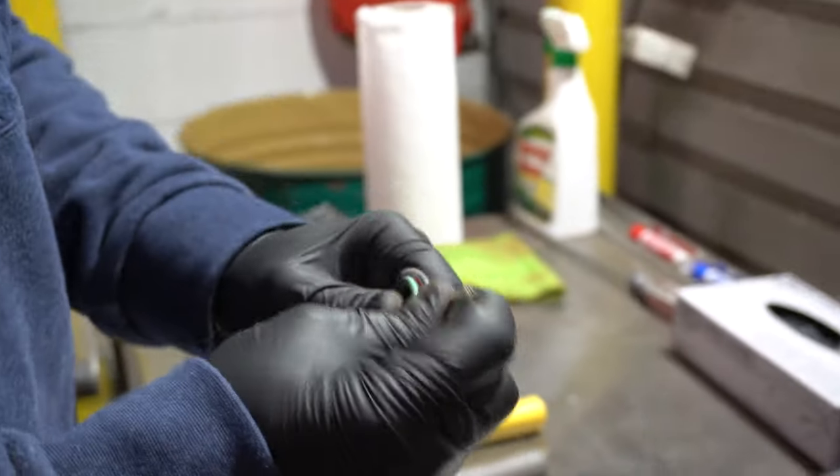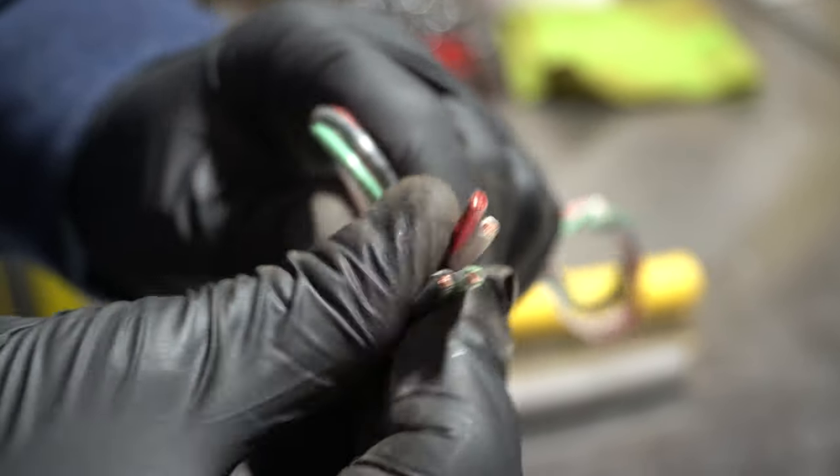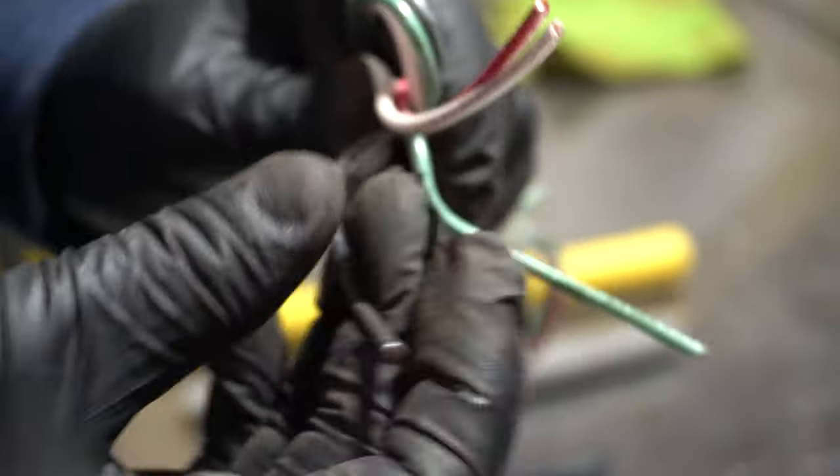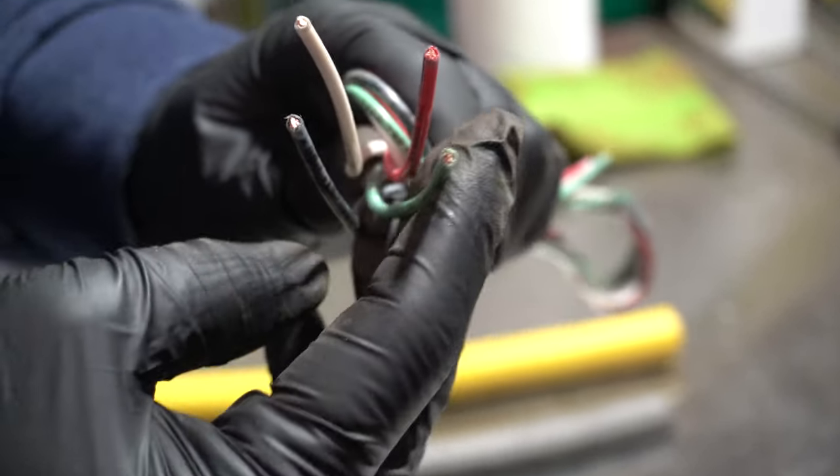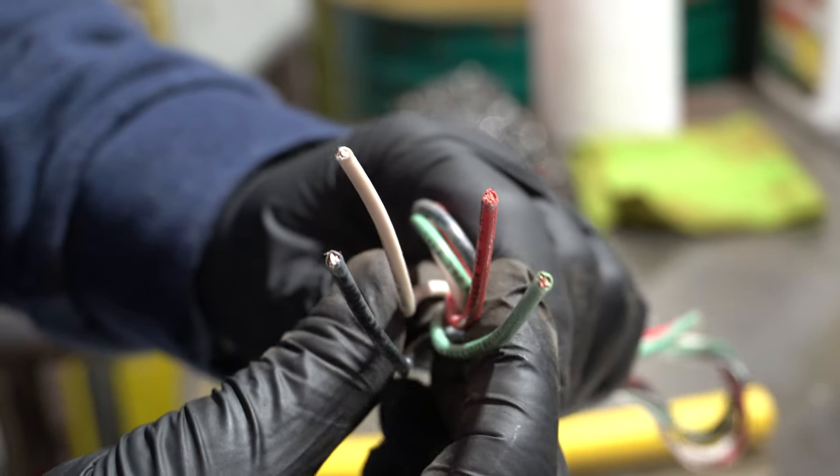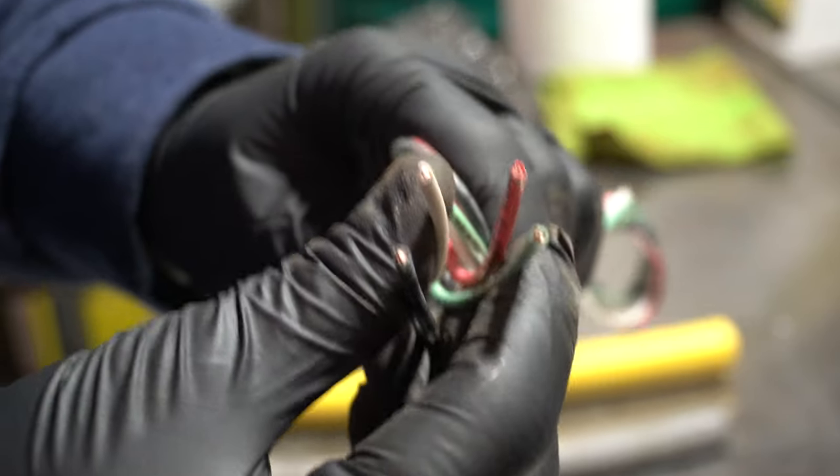Next up, like we talked about with the Romex or the BX, is your THHN wires. Green is generally going to be your ground with the other three used to have all the power currents going through. These are going to be between 70 and 80 percent copper with the balance being plastic. And almost always inside is number one bare bright copper wire.